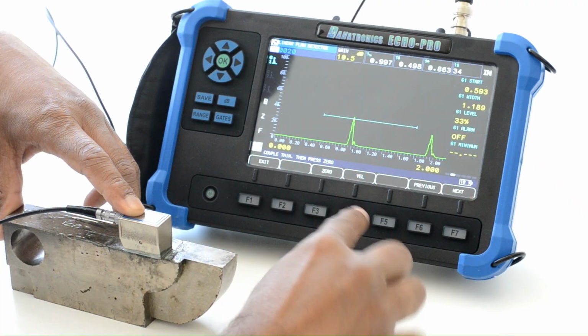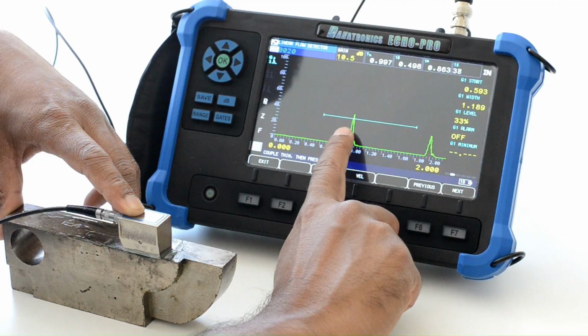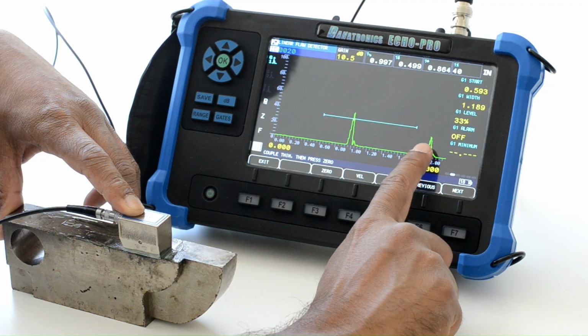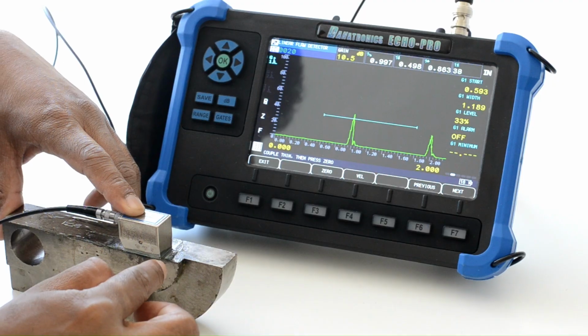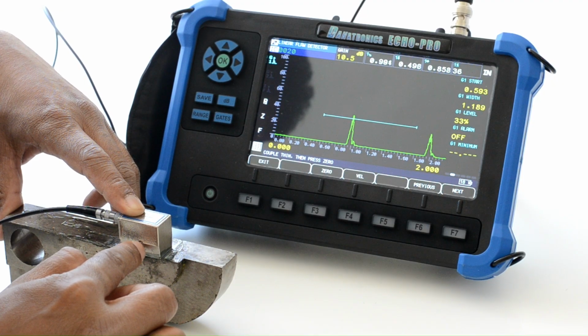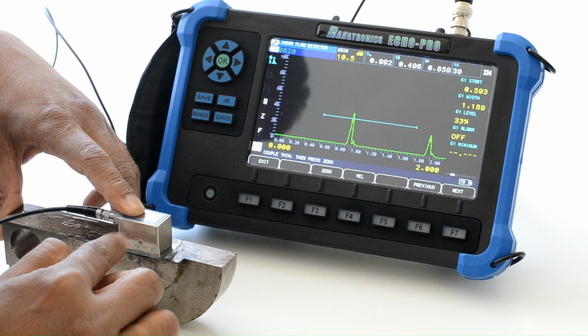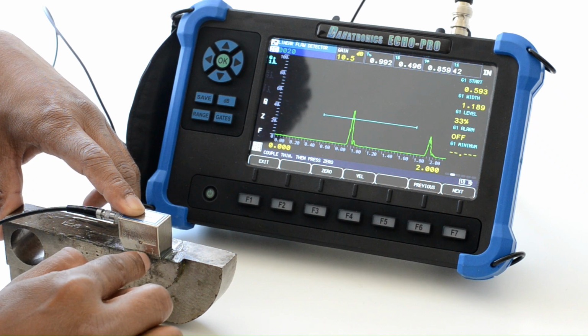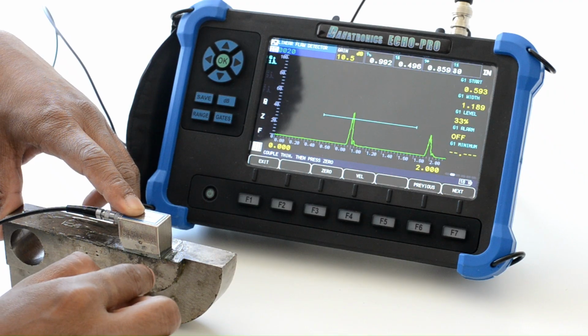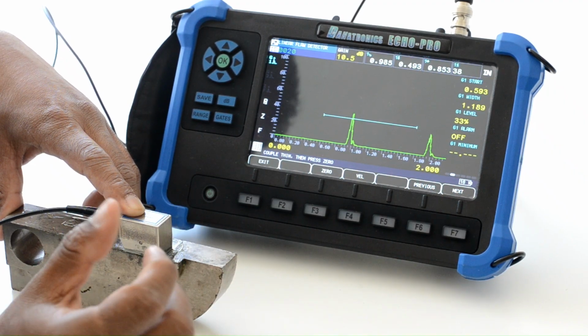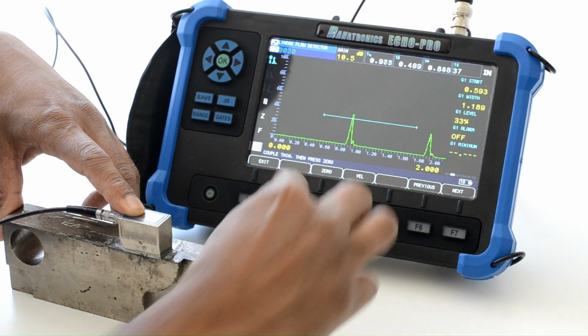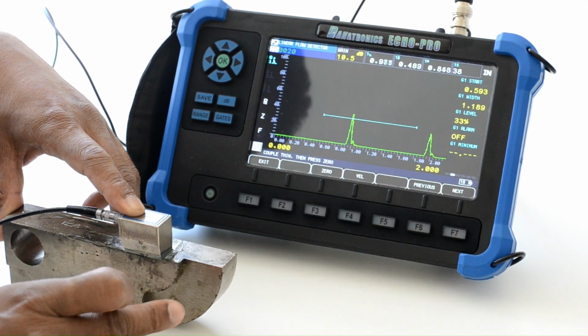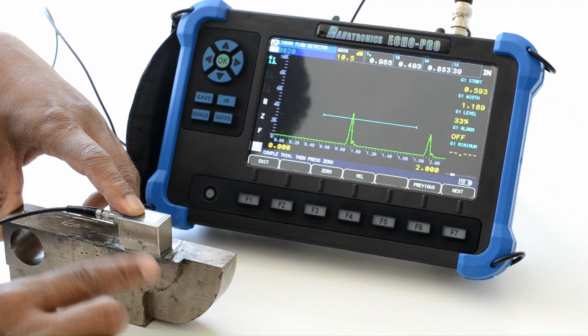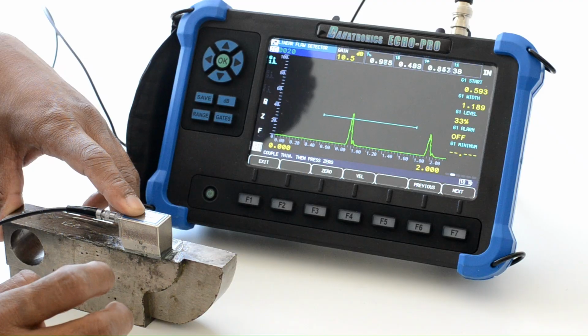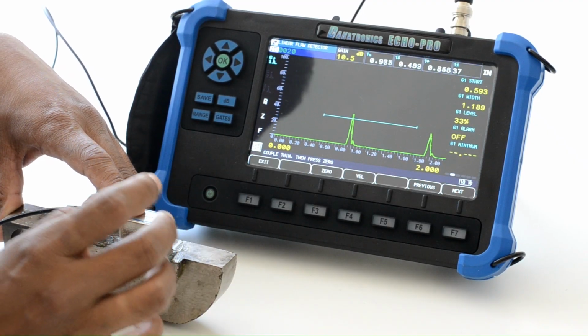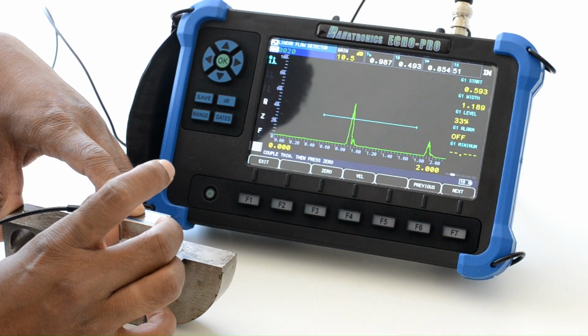Okay, so for 0, I will select this one, and for the velocity, I'll select this one. So 0 is nothing but the probe delay. From the probe, there is an element in the back of the probe, and from there to the exit point, there is a delay. So we need to find out what the delay is exactly. That is called 0, and the velocity is the velocity of this material. So this is steel, and with the calibration we will also be finding out the velocity of sound in the steel.